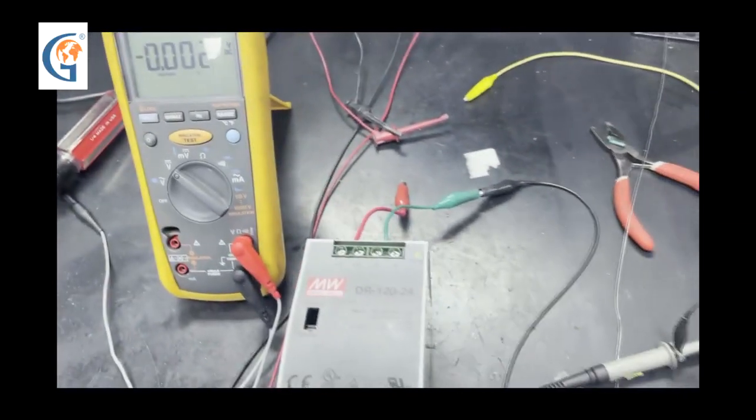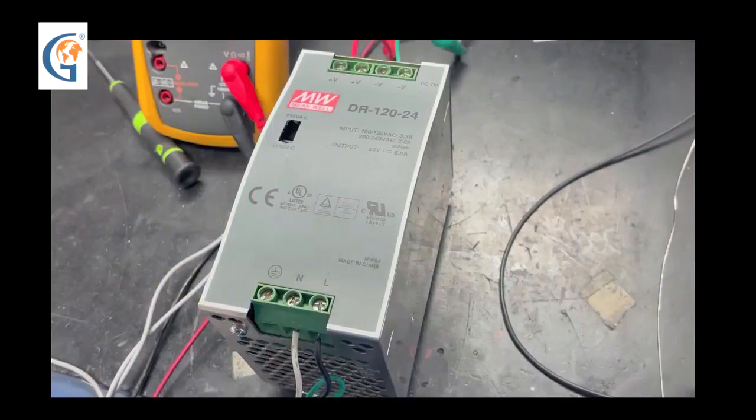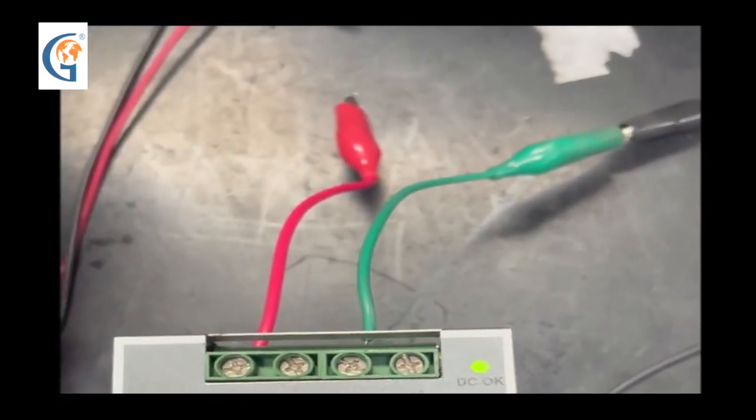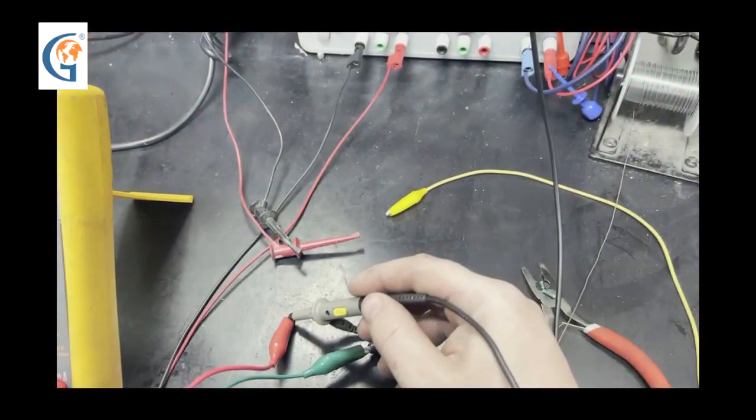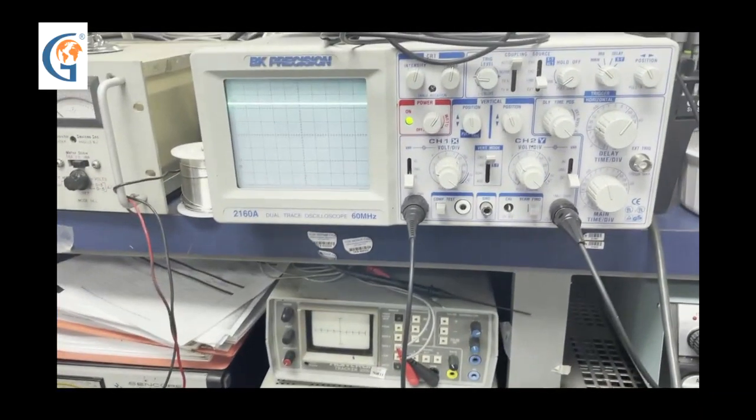However, we want to make sure it's good under a full load. Output leads and ground are hooked up. We'll use the reading on the oscilloscope to make sure we have a clean 24 volts.